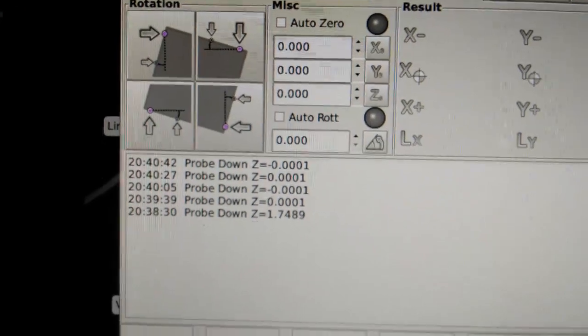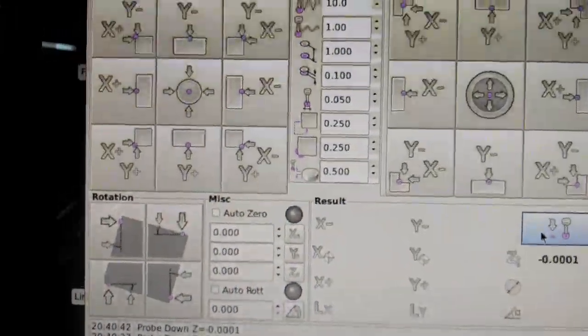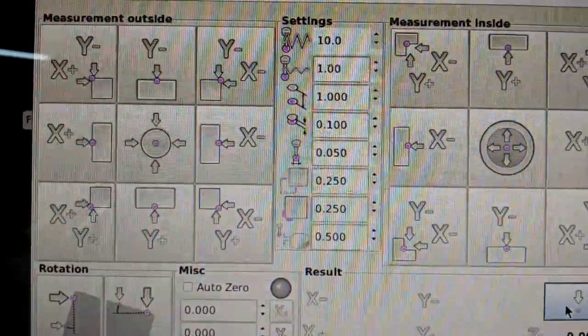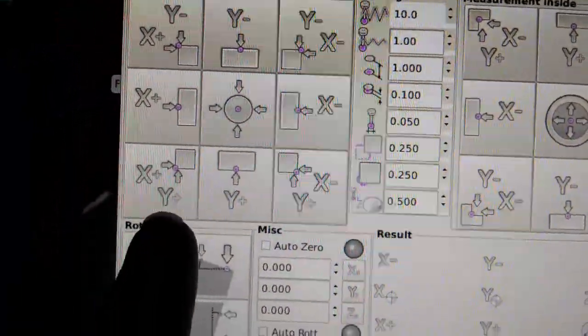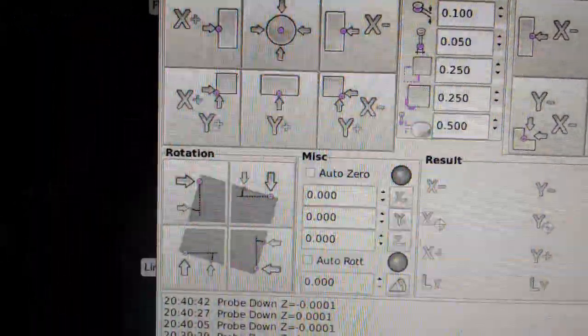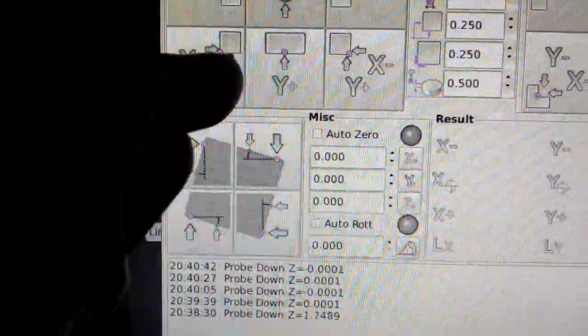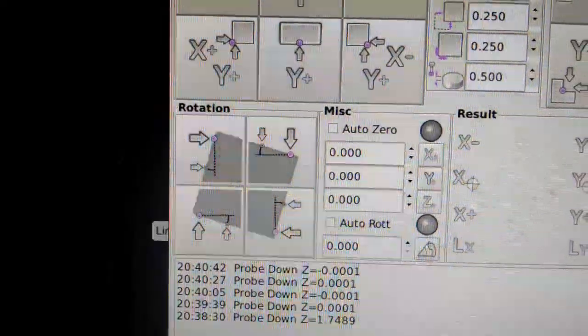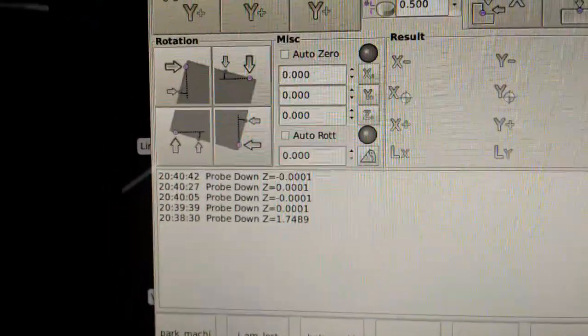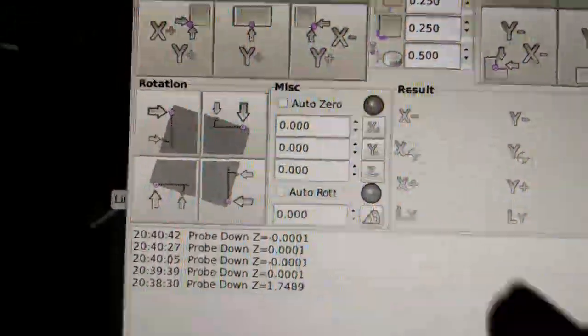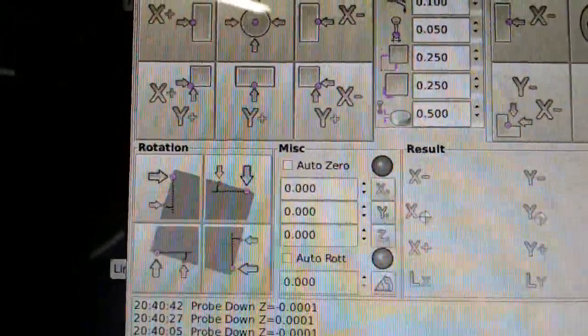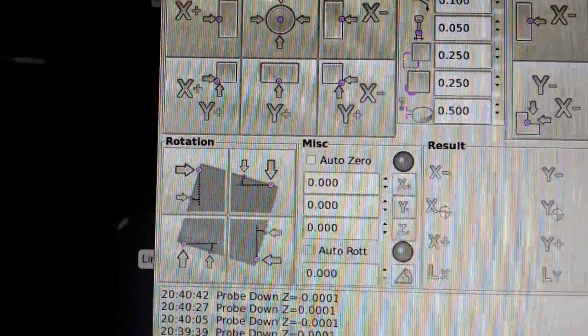$150 touch probe. So the next one that we're going to do is an outside corner, and we're going to do this outside corner here. So it's going to probe from the X direction, then come over the corner, and then probe the Y direction. So when it does this, you want your tip set up so that it is close to that corner that you're going to probe. It doesn't have to be exactly on it, but it should be close to it.